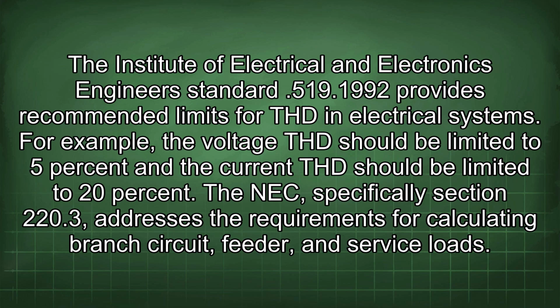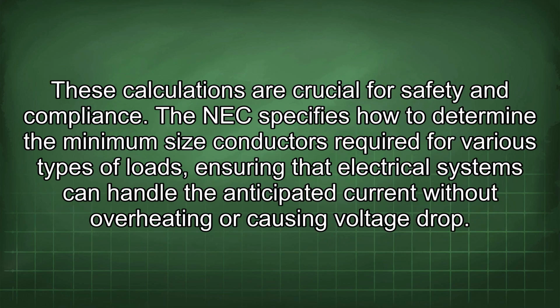The Institute of Electrical and Electronics Engineers Standard 519-1992 provides recommended limits for THD in electrical systems. For example, the voltage THD should be limited to 5% and the current THD should be limited to 20%. The NEC, specifically Section 220.3, addresses the requirements for calculating branch circuit, feeder, and service loads. These calculations are crucial for safety and compliance.